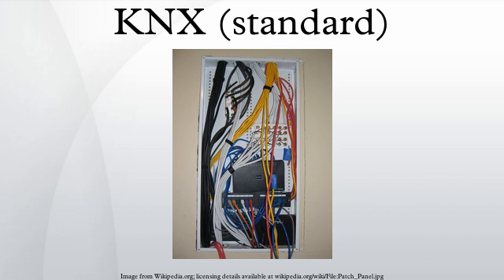KNX is a fully distributed network which accommodates up to 65,536 devices in a 16-bit individual address space. The logical topology allows 256 devices on one line. Lines may be grouped together with a main line into an area; up to 15 lines can be connected to a main line via a line coupler for a total of 16 lines. The line couplers have physical addresses from 1.1.0 to 1.15.0.